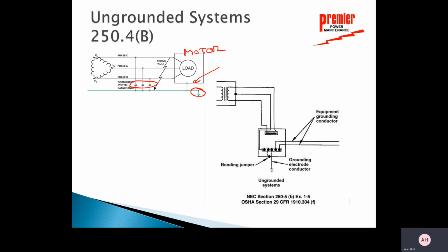But if I see here again, I get the situation where, you know what? I can carry that ground wire from the case where I started at to the case right here. And I make sure that I've got a grounding electrode. All electrical compartments are grounded, just the actual load could be isolated.